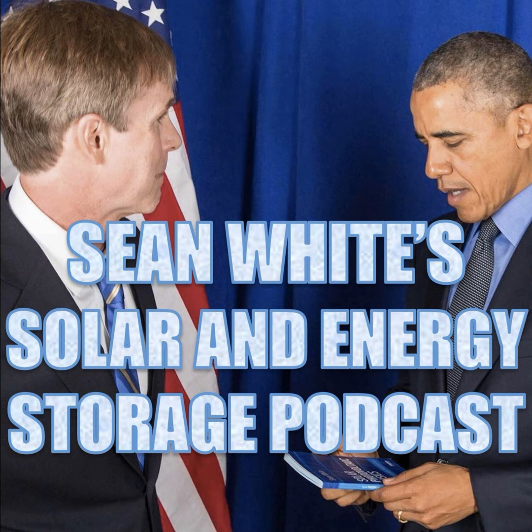A lot of this kind of goes back to having a DC energy storage system. So a lot of our energy storage systems are AC and might not have high available fault currents. So this would perhaps be changed in the next version of the NEC. If you're going to have a switch and when you turn something off, you still might have voltage on both sides of that switch, then you're going to want to see a sign that says, warning, electric shock hazard. Terminals on the line and load sides may be energized in the open position, that means off. So for instance, you might see something like this on a DC coupled system where you're going to go from your DC energy storage system to some DC bus.